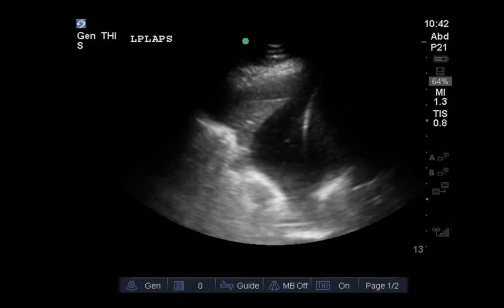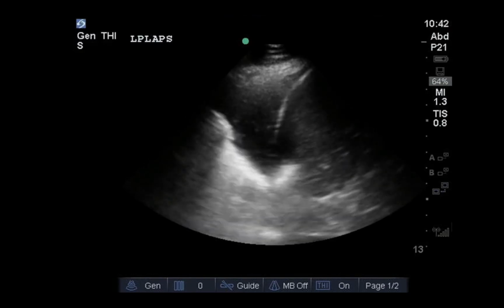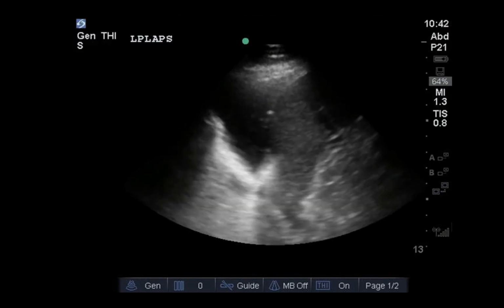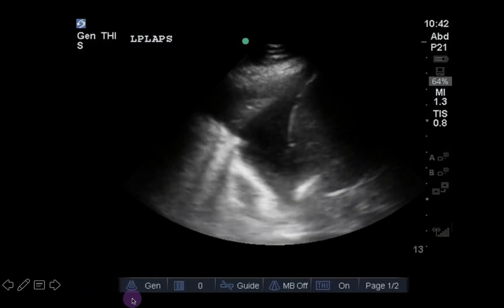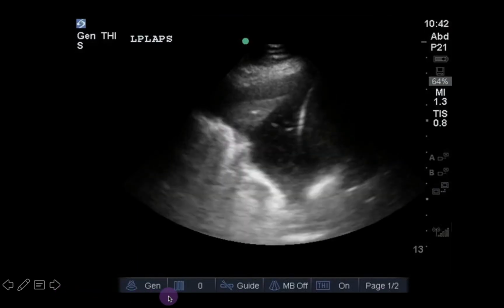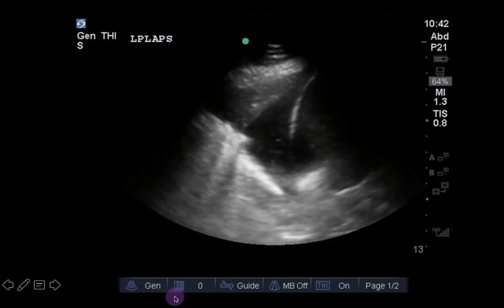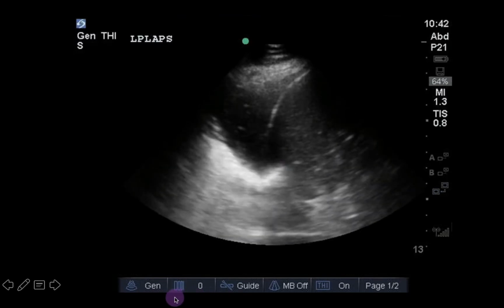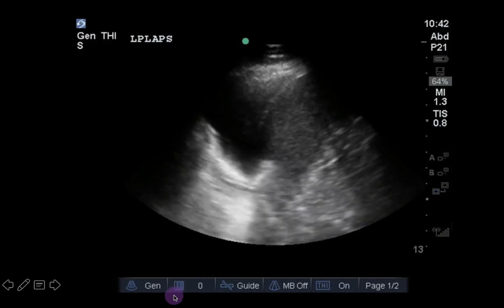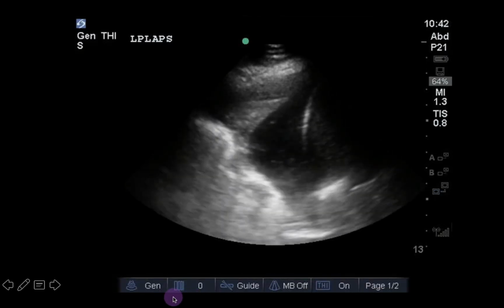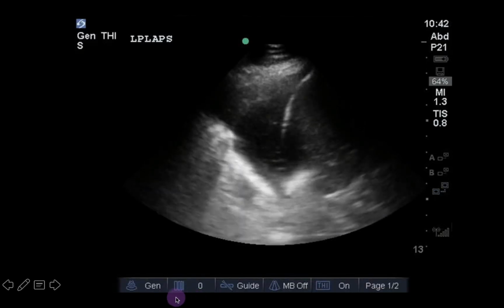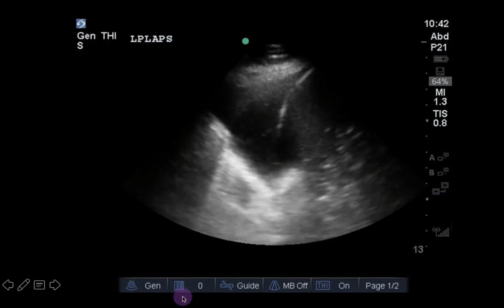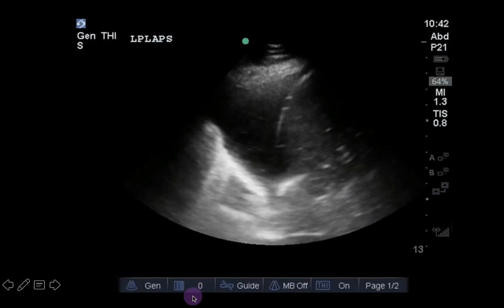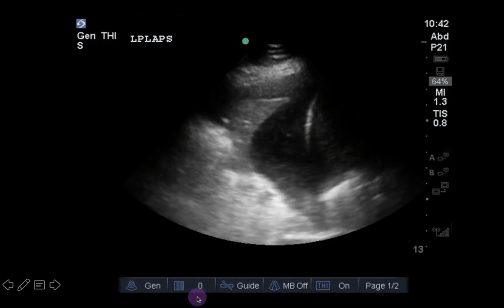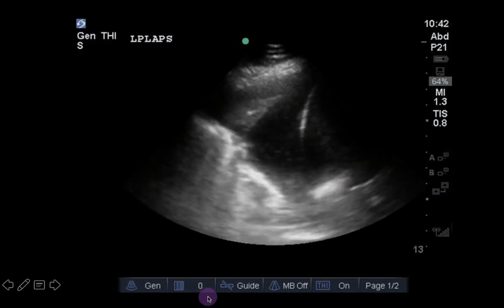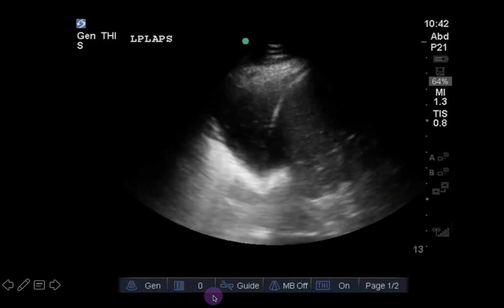Next, there's the dynamic range. This is one way to adjust the image contrast. The lower the dynamic range, the fewer shades of gray that will be in the image. So things will either be very gray, very black, or very white, and contrast will be increased. The higher the dynamic range, the more shades of gray there will be, and the less contrast there will be. Low dynamic range helps eliminate noise or bring out contrast, while high dynamic range helps bring out texture.